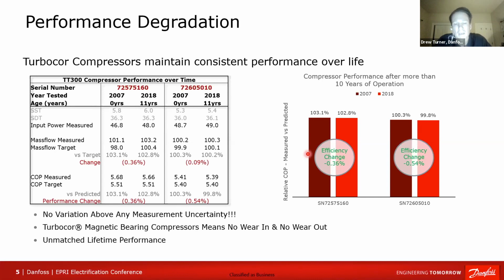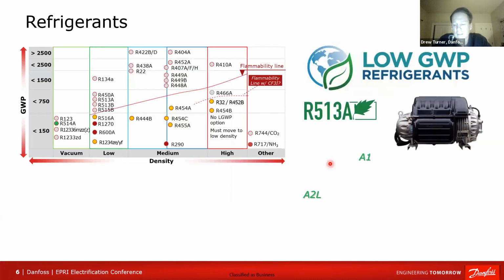But that only matters if we can prove with our own technology that it doesn't degrade in performance over time. And that's what we've been working on, testing our compressors in the factory 10 or 11 years after they were first installed, because they're also tested when they go out. Ultimately, for the other Six Sigma nerds, we want to get to a sample size more like 32, so that we can get that normal distribution. But at this point, we have 2, and we just tested 2 more, but we'll get the report on those soon. The result was about 0.4%, 0.5% performance degradation over 10 years, basically proving the hypothesis.